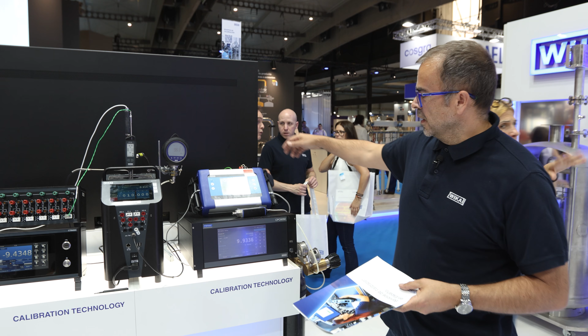Meanwhile, here we have the CPH 8000. It's a multifunction calibrator to use on site in the field, for pressure, temperature, and also electrical variables - you can do all at the same time in the field. Now it's calibrated at 10 bars, nearly done.